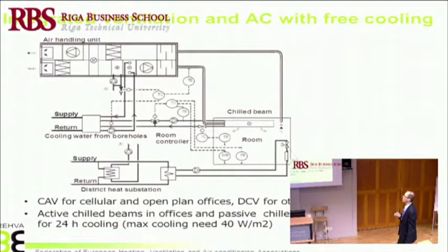And the ventilation air conditioning system is very typical, used in Nordic countries. So it is served by district heating, which will go to the radiators. There is the radiator heating in all of the building, and also indeed you have a heating coil in the air handling unit. And then for the cooling, borehole water was used. There is even no heat exchanger. This is just a water tank, and you circulate this borehole water to the cooling coil in the air handling unit and to chill beams in the rooms. So a very simple operating principle.